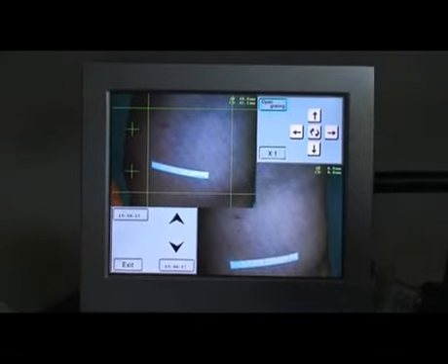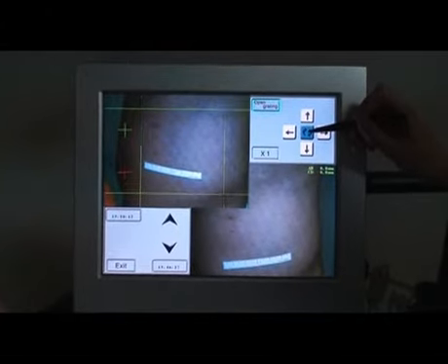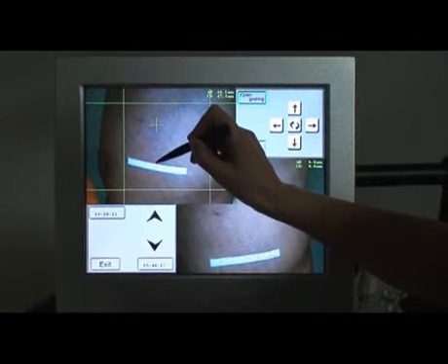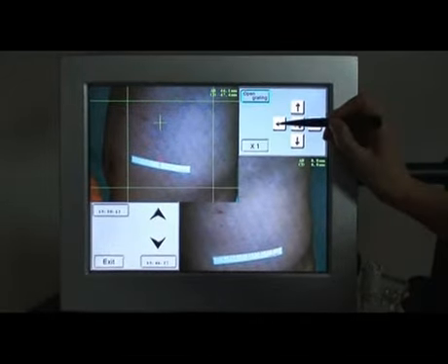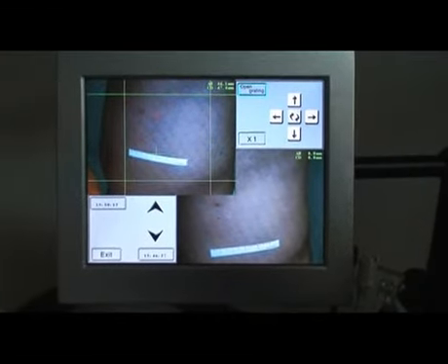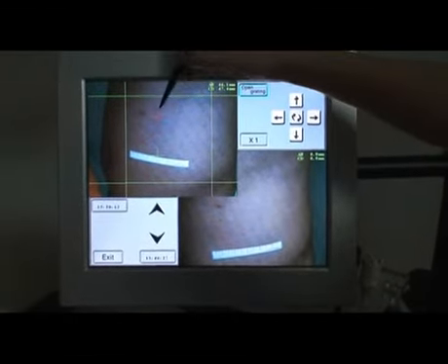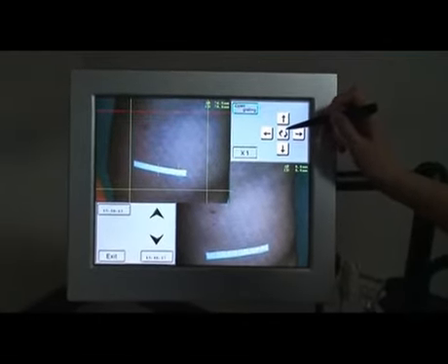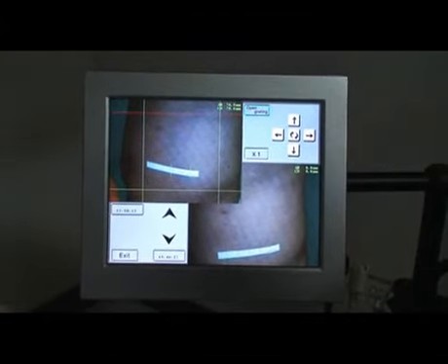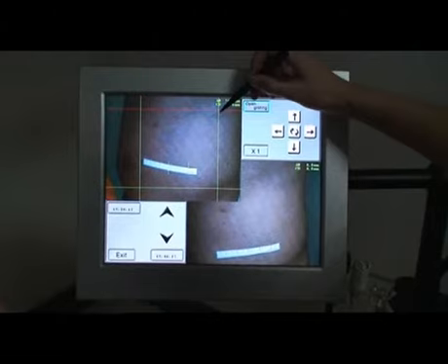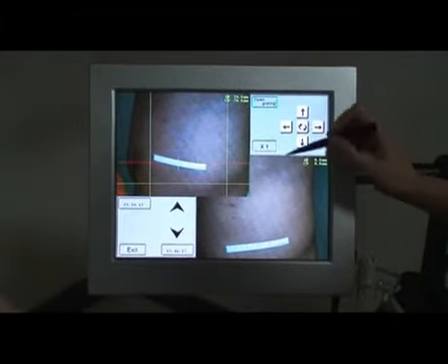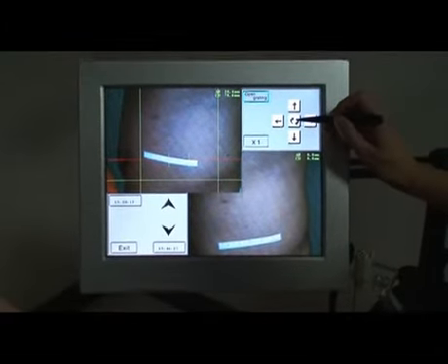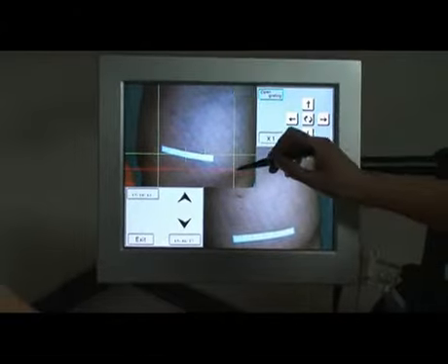Firstly, click Select key to set the reference points. Put the first reference point at the position of 0. Click the arrow to adjust. Click the Select key again. Put the second reference point at the position of 2 or 4. The two reference points should be at least 2 cm away from each other.